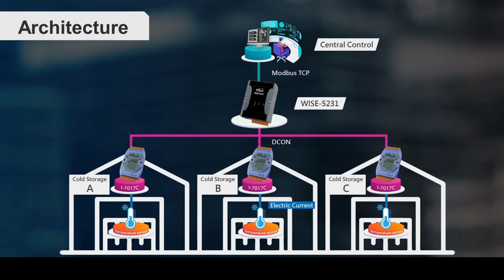i7017C is an 8-channel current input module with built-in resistor, which can collect the current signal. The client uses i7017C to collect the current signal from the temperature sensors placed in the warehouses. The collected signal is then transmitted to WISE5231 via DCON, and then sent to the control center through Modbus TCP. The management personnel can monitor the real-time temperature of the 3 warehouses remotely at the same time in the control center, with no need to shuttle between warehouses and control center to record the temperature data.